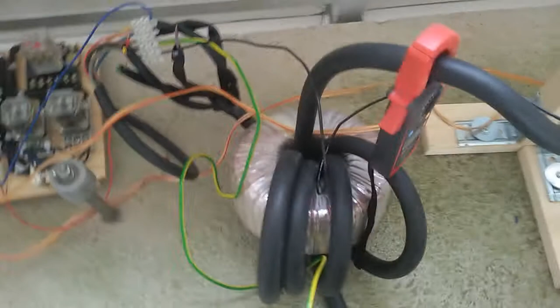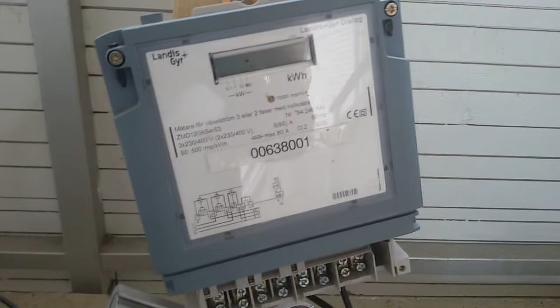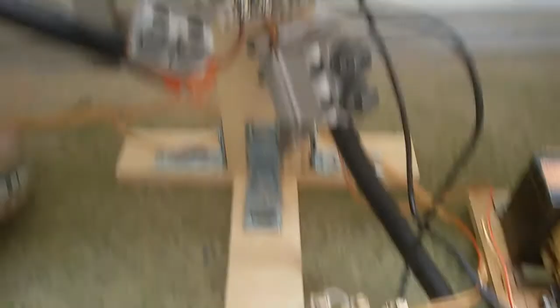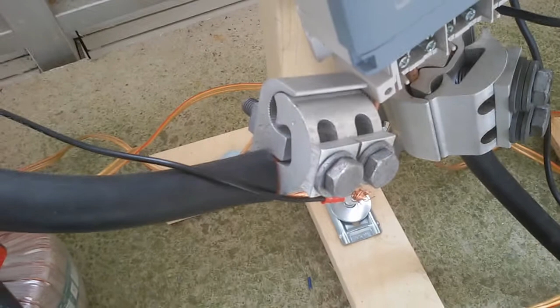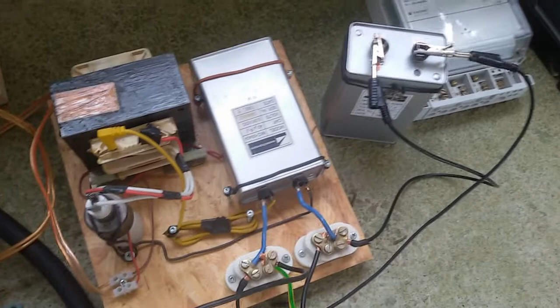But now it's done, and it's time to blow the electric meters. So here's the setup: the feeding wire, and that's a controller for charging the surge capacitor. I've got the high current transformer with an amp meter on it, short connections to the electric meter, a Landis and Gyr one. There's the wire for the 230 volts, and there's the high voltage spike wires for a surge, 2 kV, 3 kV, going into a contactor, then a transformer and the two capacitors.